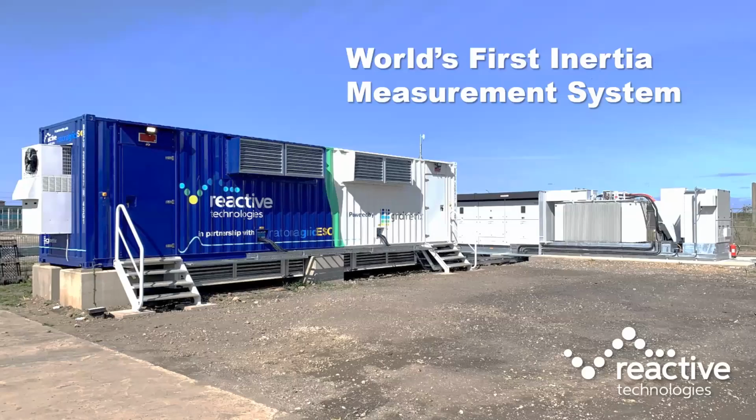Second by second, whereas at the moment, we obviously just analyze peak points, so every 4 hours, whatever. But with this inertia monitoring kit, we will be able to get that real-time measurement, which obviously helps us understand how close to the cliff edge we are, because the modeling is great, but actually we could be a long way from the cliff edge and push the system harder, or we could have further to go.